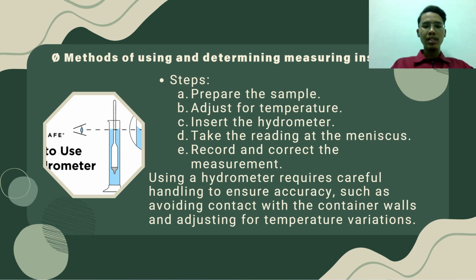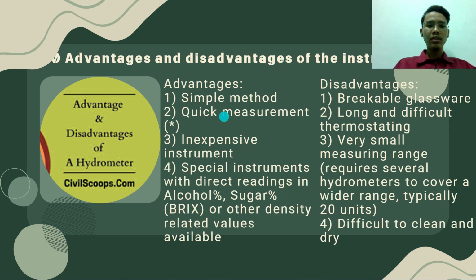Next slide is the advantages and disadvantages of the instrument. So the advantages of using this hydrometer are that it is a very simple method, quick measurement, and an inexpensive instrument, with special instruments giving direct reading in alcohol, sugar, or other density-related values available. The disadvantages of using the hydrometer are that it is breakable glassware, so we need to handle the instrument carefully to make sure it does not break. Also, long and difficult thermostating, a very small measurement range that requires several hydrometers to cover a wider range, typically 20 units, and it is difficult to clean and dry.